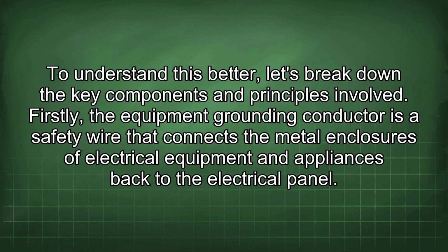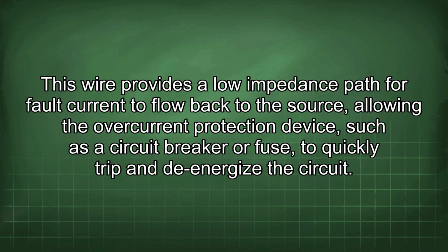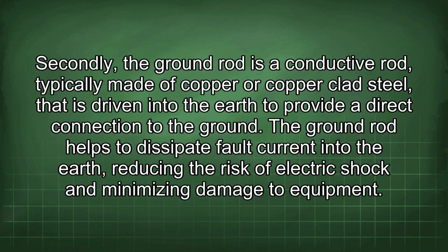Firstly, the equipment grounding conductor is a safety wire that connects the metal enclosures of electrical equipment and appliances back to the electrical panel. This wire provides a low impedance path for fault current to flow back to the source, allowing the overcurrent protection device, such as a circuit breaker or fuse, to quickly trip and de-energize the circuit. Secondly, the ground rod is a conductive rod, typically made of copper or copper-clad steel, that is driven into the earth to provide a direct connection to the ground.